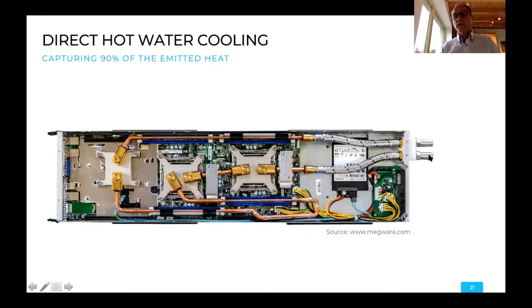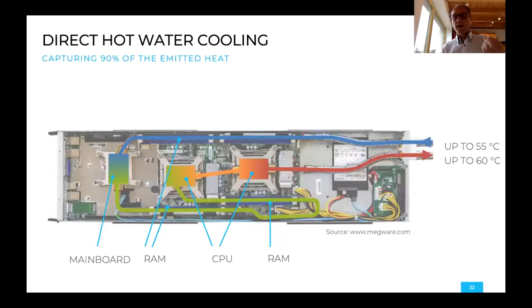So you connected it, and then you get the heat from the memory components here. You get the heat from these components on the back side of this server. These are all the InfiniBand or Ethernet chips that are cooled by this cooling loop. And then the water flows further to the first CPU, the voltage regulator, to the second CPU, to another voltage regulator, across the SSD drives, and basically gets out of the server. So with this kind of setup, we remove all the fans. So that makes this server very low noise, but we also have a very, very slim and compact way of cooling these servers.